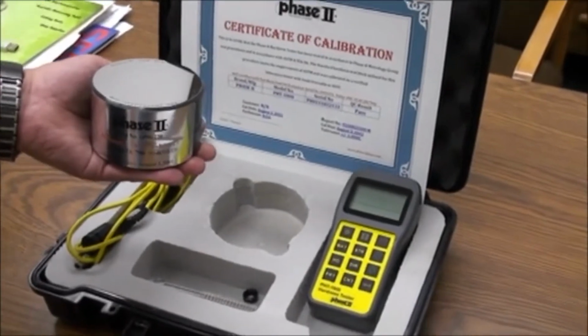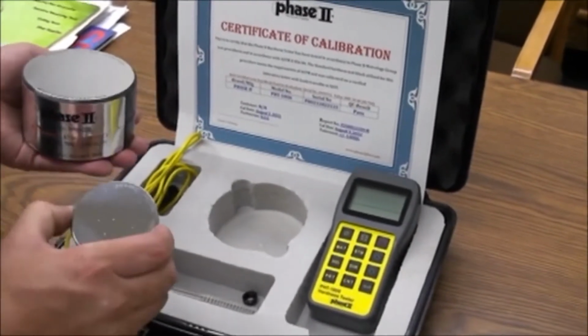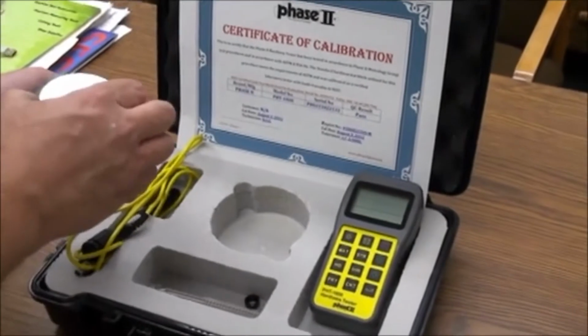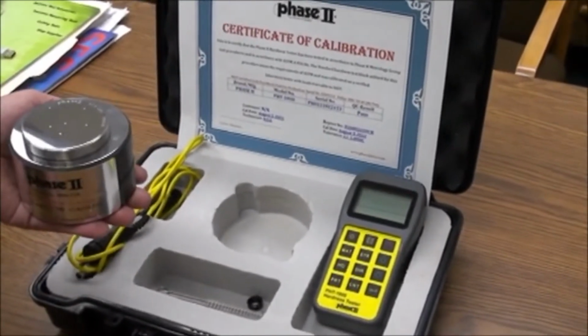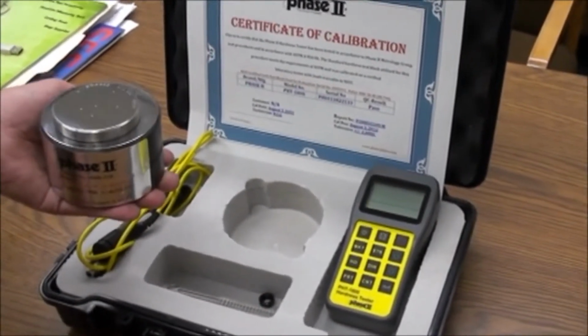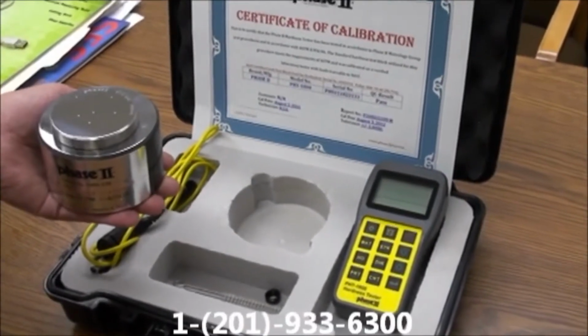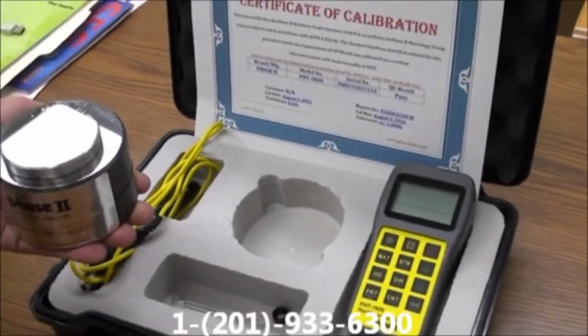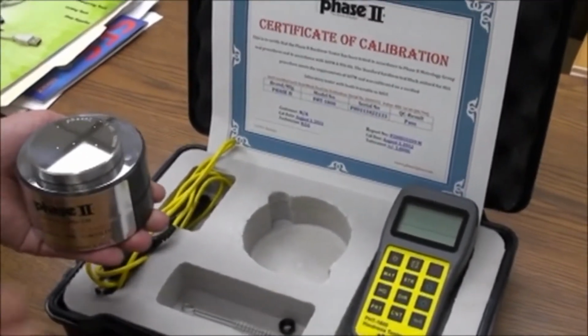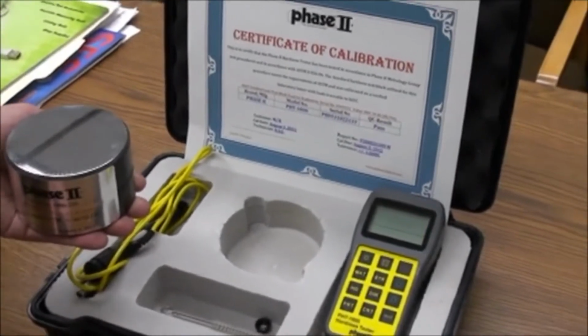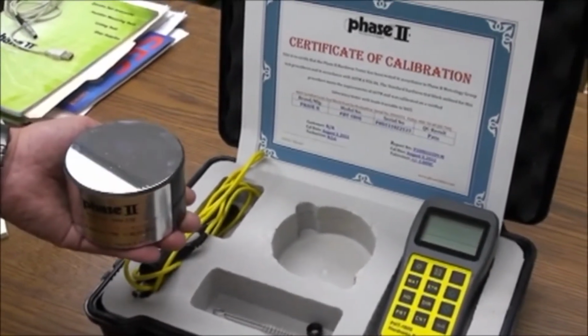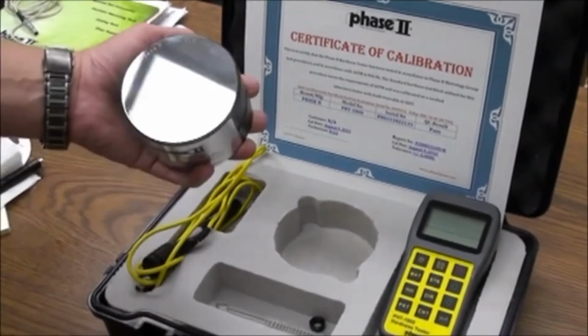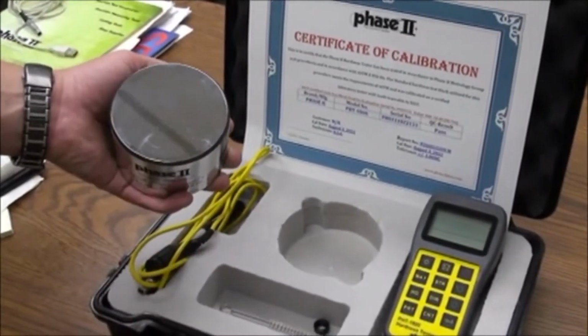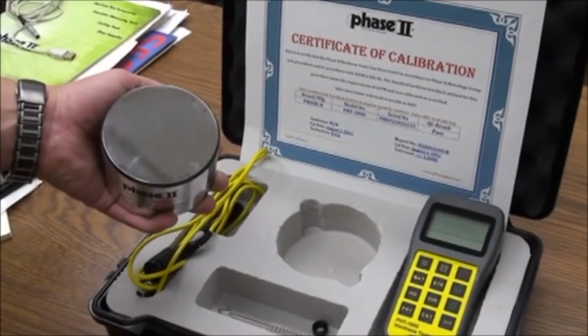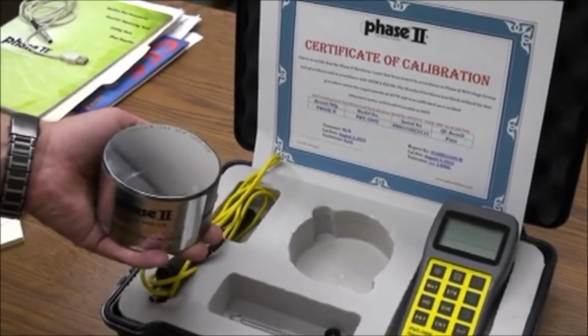Parts with mass a little less can be affixed, if possible, to something of larger mass, to obtain performance. Should you have workpieces that are not close to such mass, please contact Phase 2 and inquire about our ultrasonic portable hardness testers. The next parameter is surface roughness. Surface roughness should average a 2 micron or 80 microinch finish or better using the standard impact probe. Optional probes such as the G probe can handle rougher surfaces such as on rough castings.